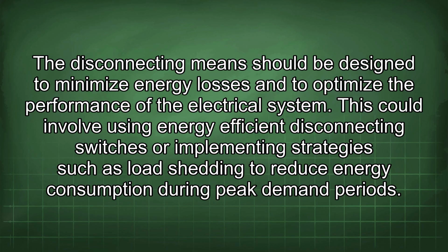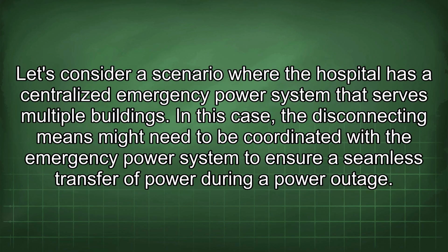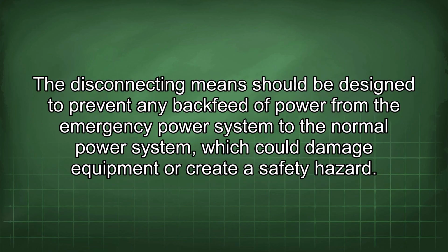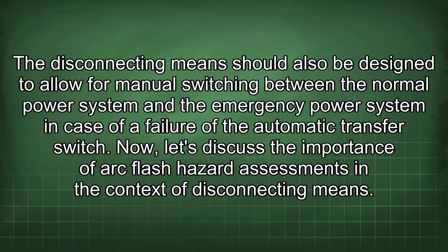Let's consider a scenario where the hospital has a centralized emergency power system that serves multiple buildings. In this case, the disconnecting means might need to be coordinated with the emergency power system to ensure a seamless transfer of power during a power outage. The disconnecting means should be designed to prevent any backfeed of power from the emergency power system to the normal power system, which could damage equipment or create a safety hazard. The disconnecting means should also be designed to allow for manual switching between the normal power system and the emergency power system in case of a failure of the automatic transfer switch.